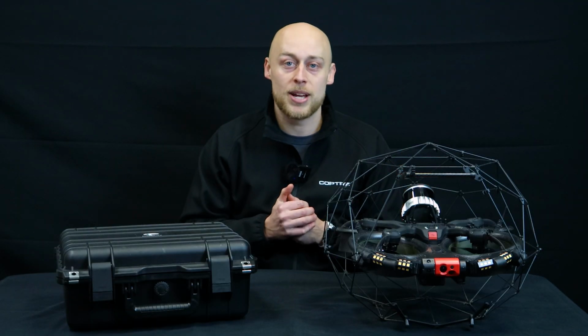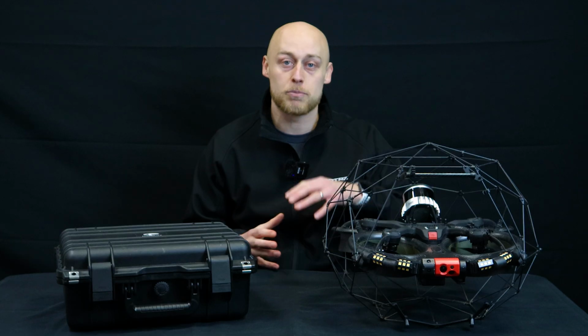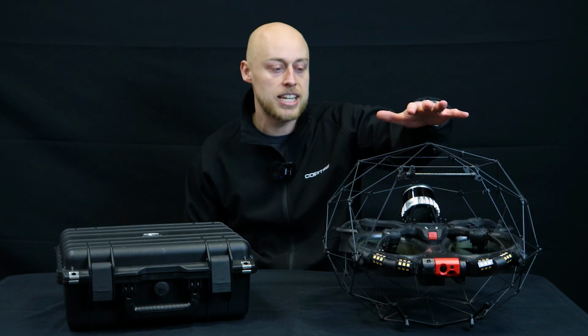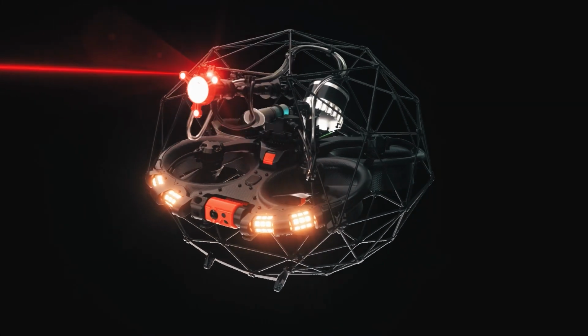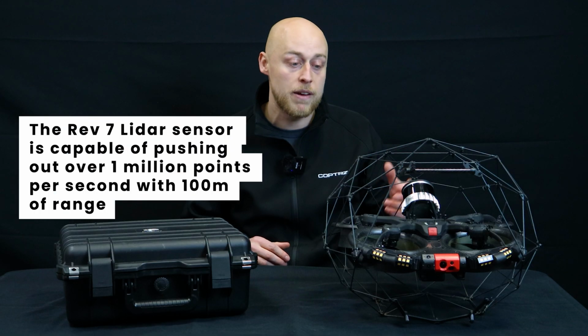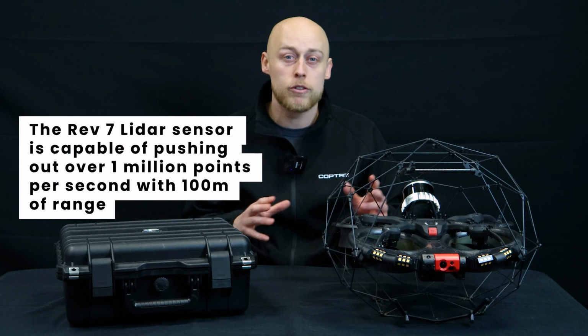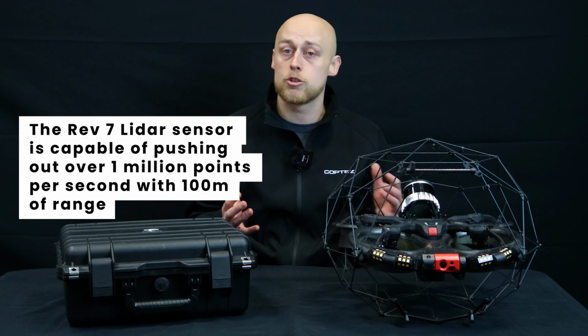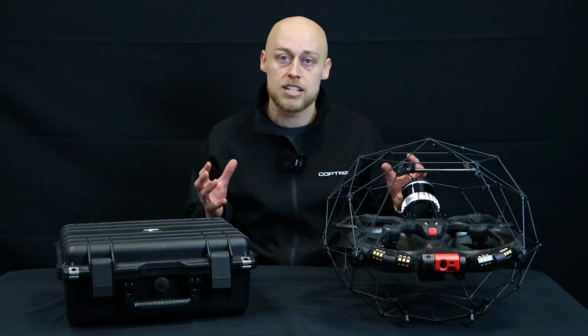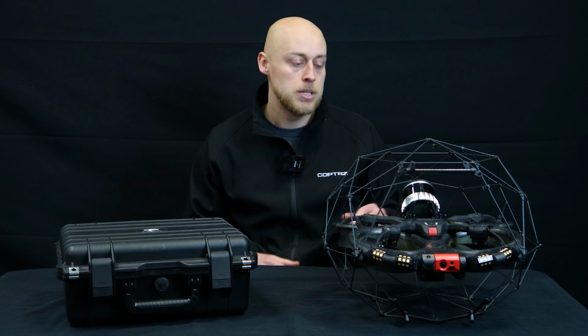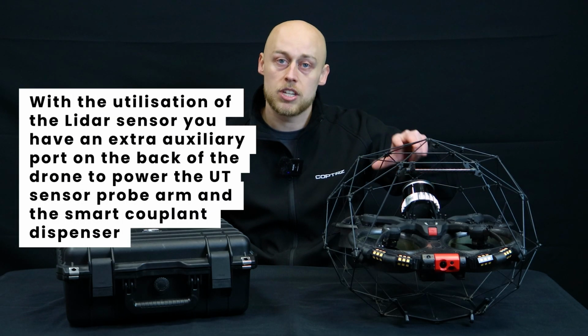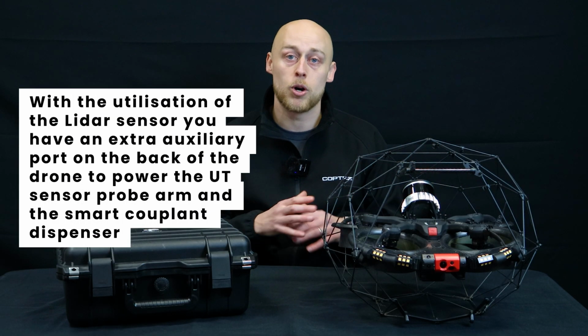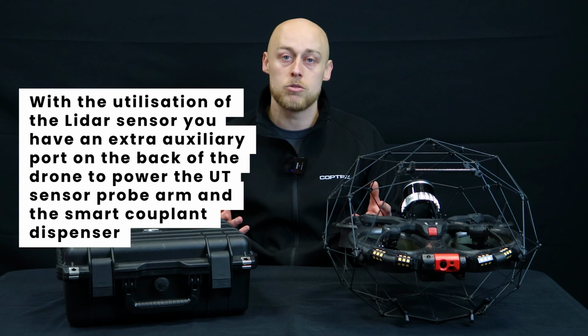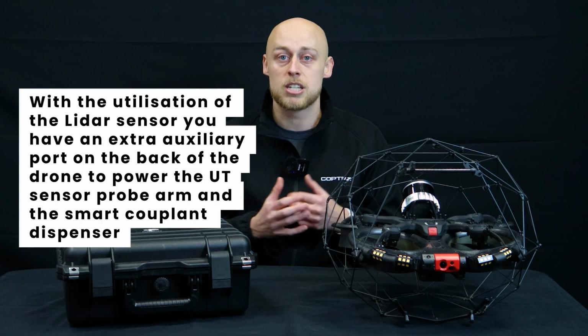So first step, what we'll go into straight away is attaching the probe device to the Elios 3, which we see here. We have currently the Elios 3 system with the survey grade payload, so the Rev 7, which pushes out over 1 million points per second, 100 meters of range. So when you are doing these more complex environments, taking the UT data, you can really utilize all of the data with it working in tandem. With the utilization of the LiDAR, you actually have an extra auxiliary port at the back, which is where it powers through the UT probe arm and also the smart couplant dispenser.